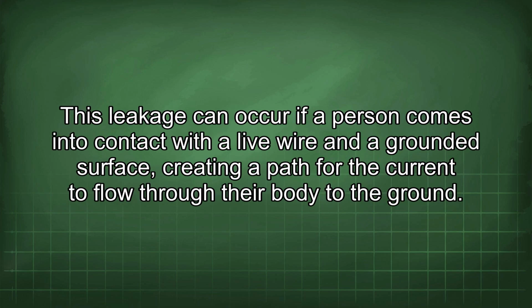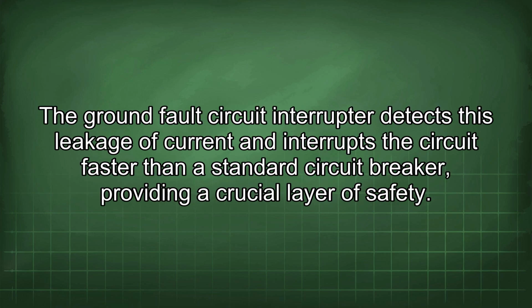This leakage can occur if a person comes into contact with a live wire and a grounded surface, creating a path for the current to flow through their body to the ground. The ground fault circuit interrupter detects this leakage of current and interrupts the circuit faster than a standard circuit breaker, providing a crucial layer of safety.